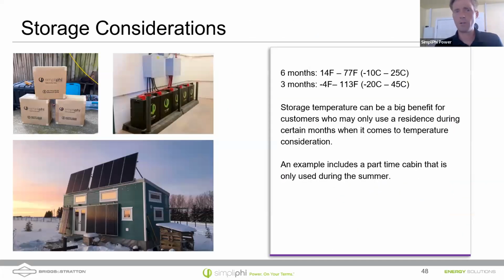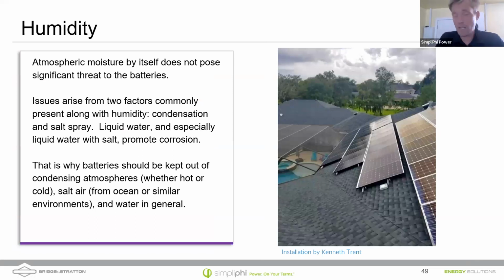I'm happy to answer it in more detail later, but I wanted to jump right into what Daniel was talking about. If you're going to be using the batteries in very low temperatures, these batteries can be stored in quite cold temperatures. We do just recommend that you try to run them through a charge cycle. Unlike lead acid batteries, the self-discharge rate of lithium batteries is very slow. Typically around 1% a month is the figure that engineering has given us, and they'll stay charged for a long time. Humidity is not often a huge consideration unless you live near the coast and you have a lot of salt water in the air. Then you might want to make sure that the batteries are protected from high levels of humidity that can come in with early morning fog from coastal communities.